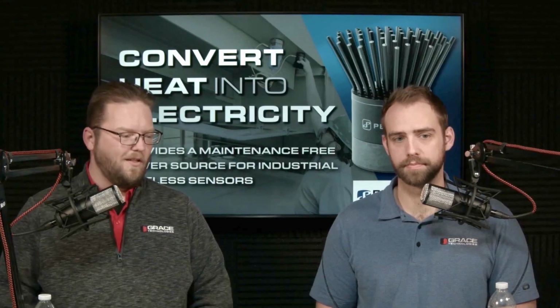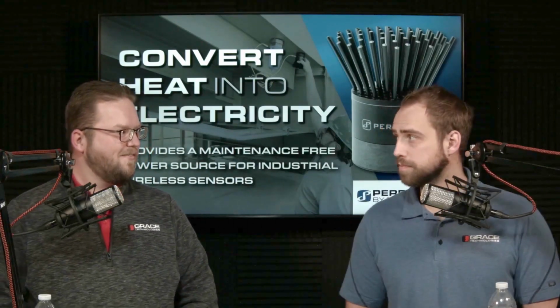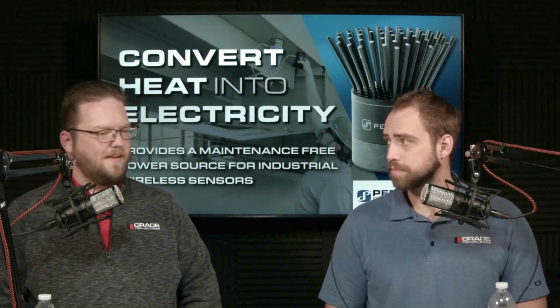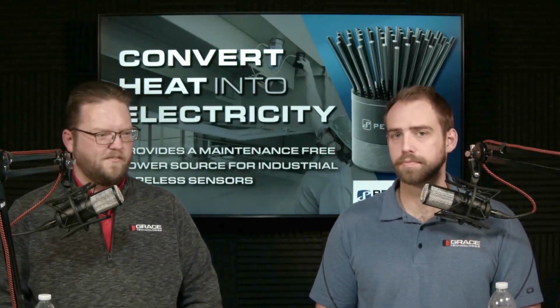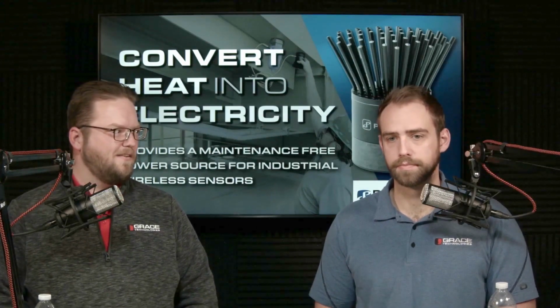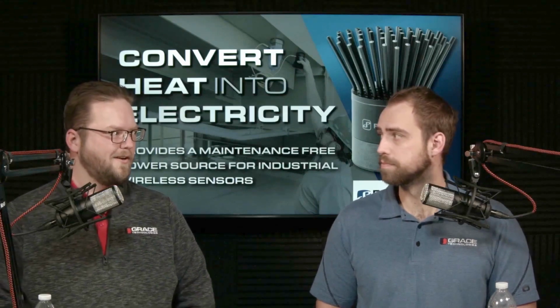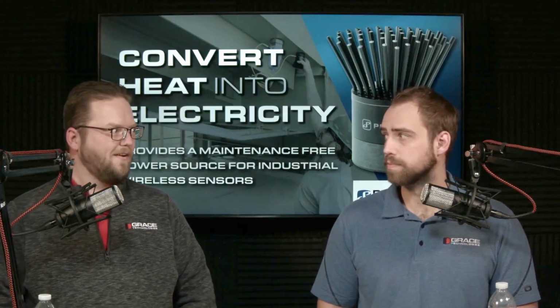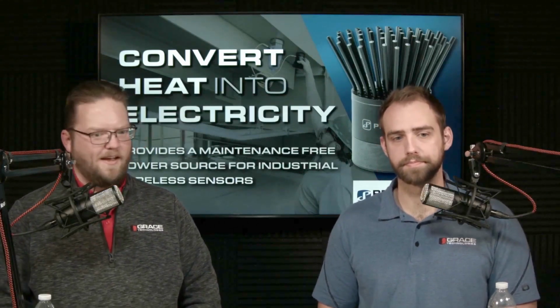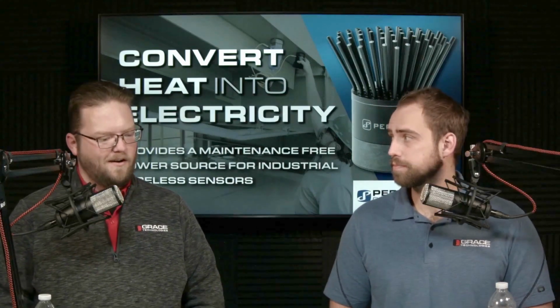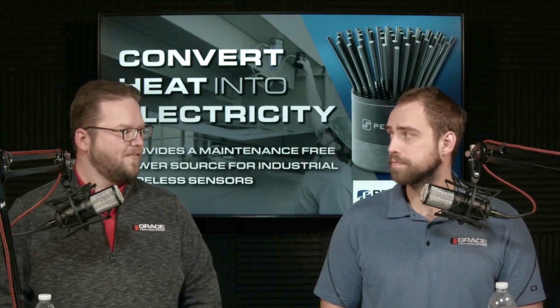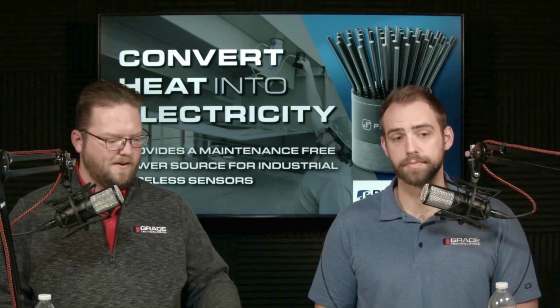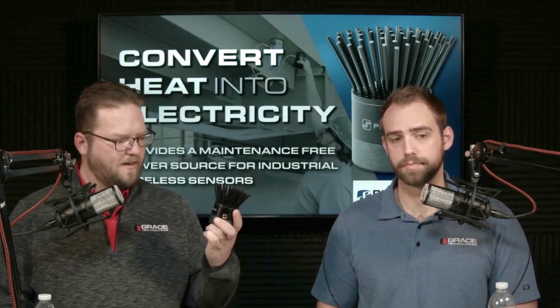When you look at the cost analysis of an install, if you take out the need to run power to a location, especially if it's hazardous, and take out the need to go replace batteries every year or two in a hazardous or extreme height location, we can knock off near $10,000 of an install of a wireless transmitter, and you'll never have to go back and maintain a battery.